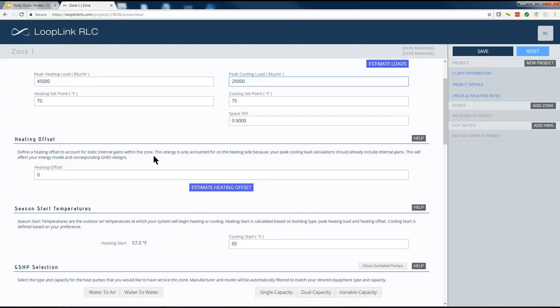On the heating side, worst case is generally on the coldest day of the year. But when you don't have any internal gains, you don't have any solar gains on the house, you're not accounting for internal heat generation due to people, lights, appliances, etc. This is an absolute worst case number. But generally speaking, that peak heating load doesn't necessarily reflect actual usage of the building, right? From normal everyday usage, people living in the space, etc. And that's exactly where this heating offset value comes in.